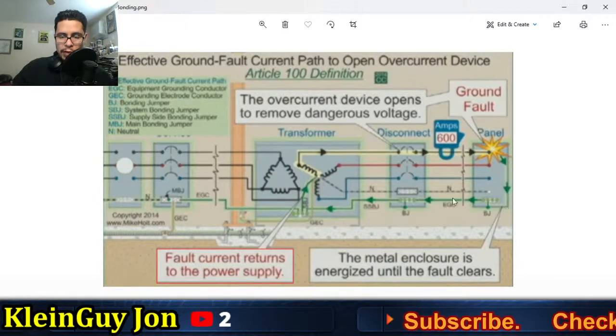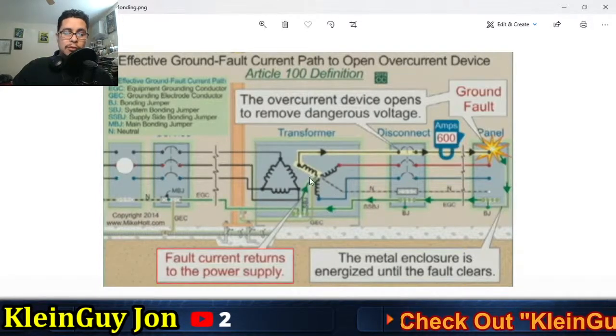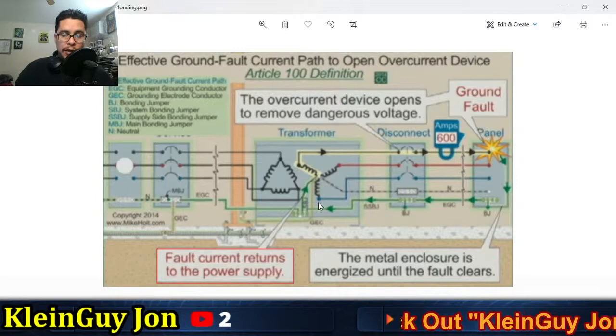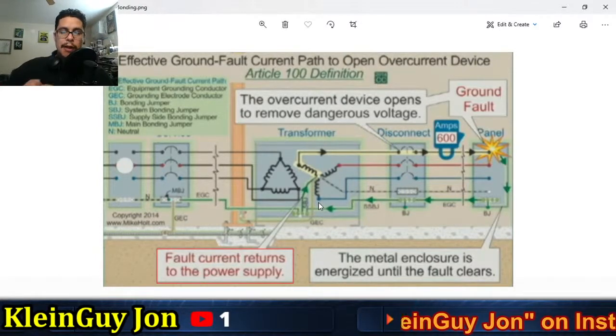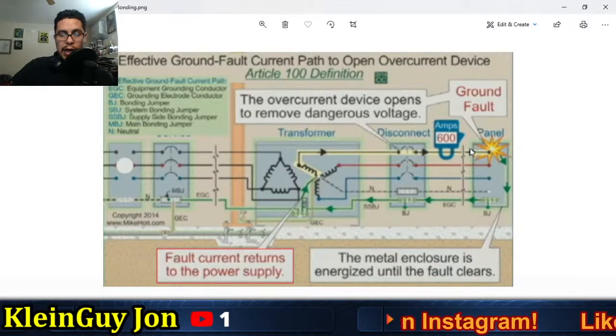Electrons are going back to the source. They're going through, because everything now here is connected. All the metal parts are connected, and that's what we call bonding. We're bonding everything together when it comes to installing electrical equipment.